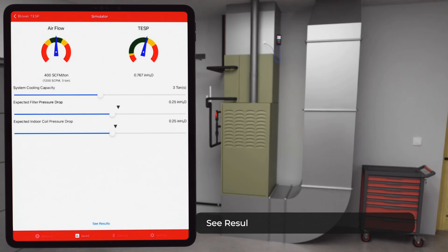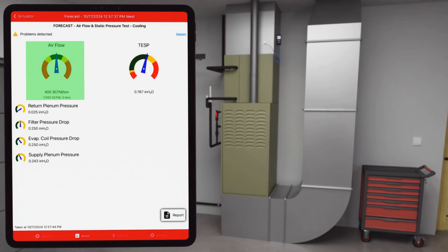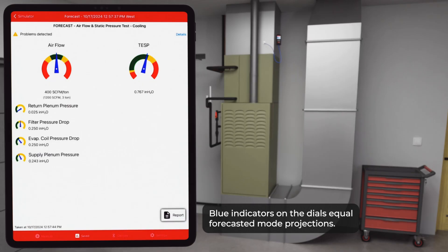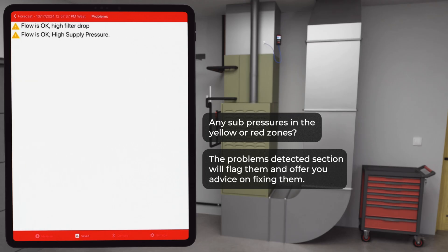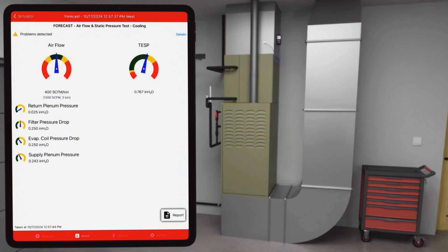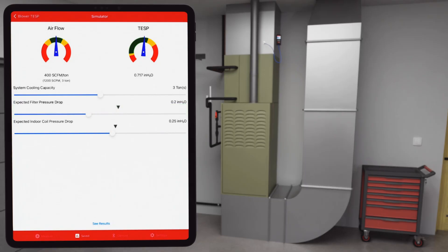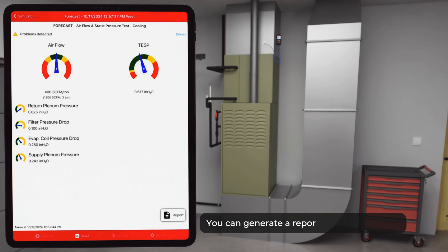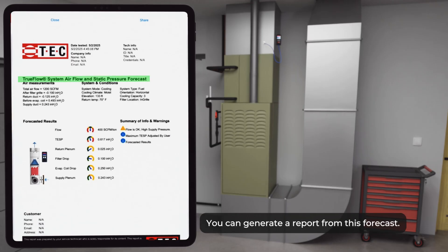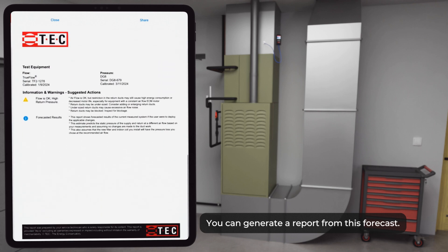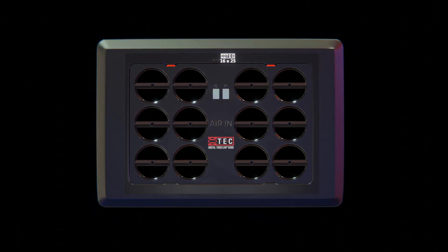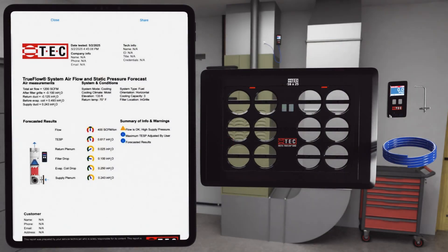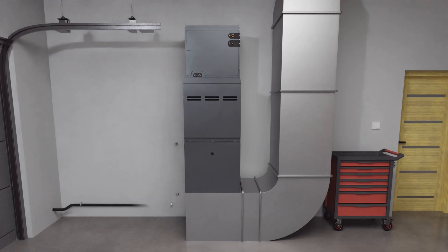Once the sliders are set, select continue to advance the app. This will generate projected airflow and TESP readings along with updated sub-pressures. Blue indicators in the dials equal forecasted mode projections. If any sub-pressures are in the yellow or red zones, the problem detected section will flag them and offer advice on how to fix them. For this install, we're going to show a TESP improvement by adjusting the filter slider to a lower pressure drop. Finally, you can generate a report from this forecast. It's labeled clearly as a forecast report, making it easy to present, save, or share with others.